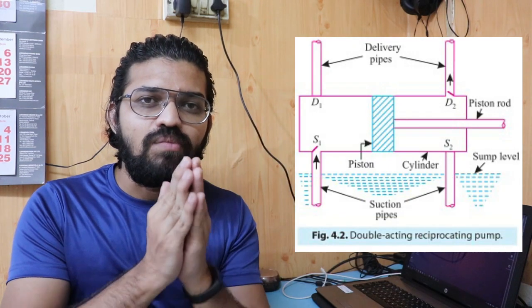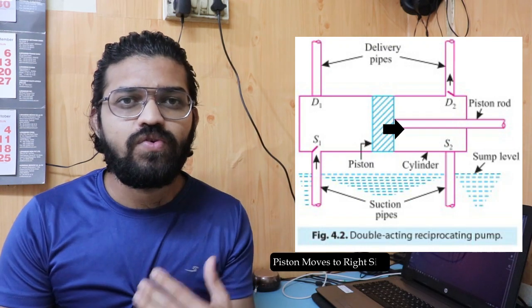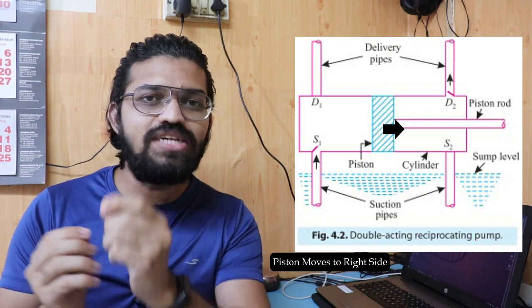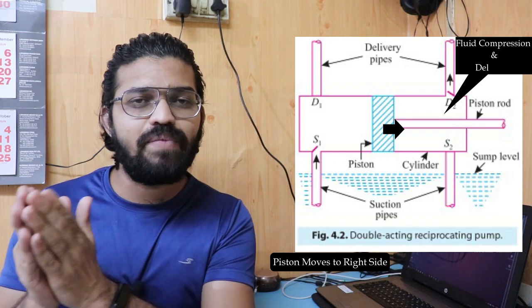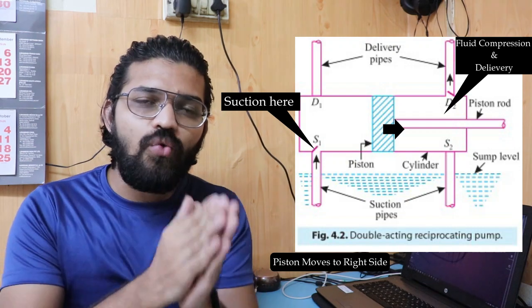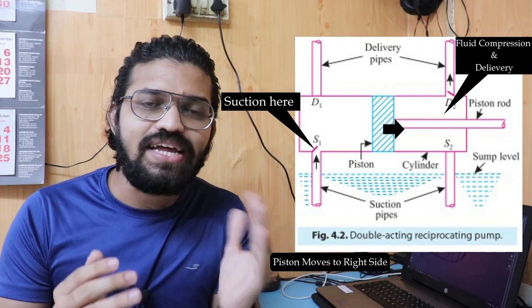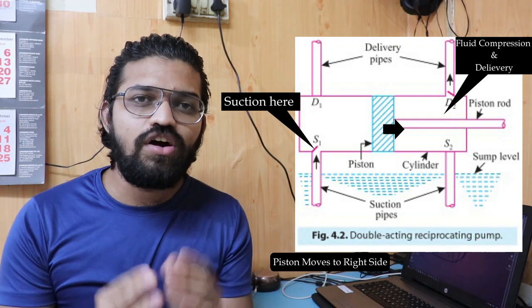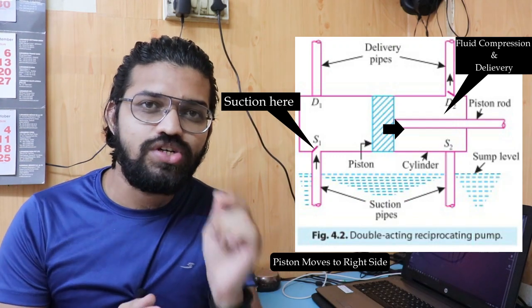So on the right side of the piston suction occurs, while at the same time on the left side discharge occurs. When the piston moves towards the right side, the same process reverses — the fluid on the right side gets compressed and discharge occurs on the right, while suction occurs on the left side. This cycle gets repeated as the piston reciprocates in the cylinder.